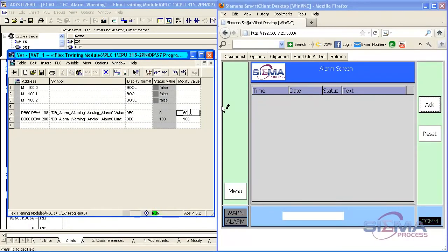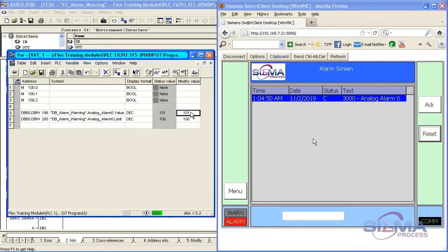After that, we're going to have an example of an analog alarm, where if your value is out of the limit, you're going to have the alarm coming up, and if the value is in the limit, then the alarm will be deactivated, and then you have to go and acknowledge the alarms. I'm not personally that much of a fan of using analog alarms. I prefer to combine that with the digital alarms, because it gives me more options and more flexibility to deal with the alarm.